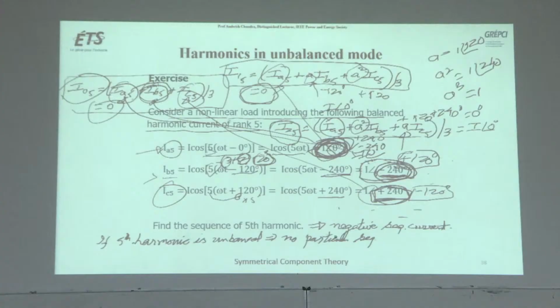Is it clear? So you have to see the phase shifting with A, and finally you will see the negative sequence of the fifth harmonic has the value A. It means the fifth harmonic is a negative sequence current. So this is how mathematically you can see if the fifth harmonic is positive sequence, zero sequence, or negative sequence.